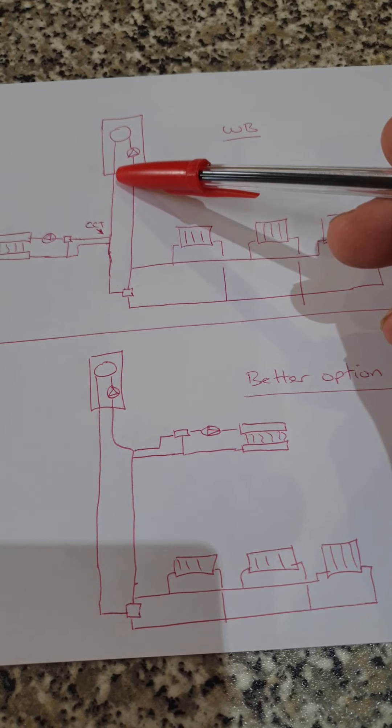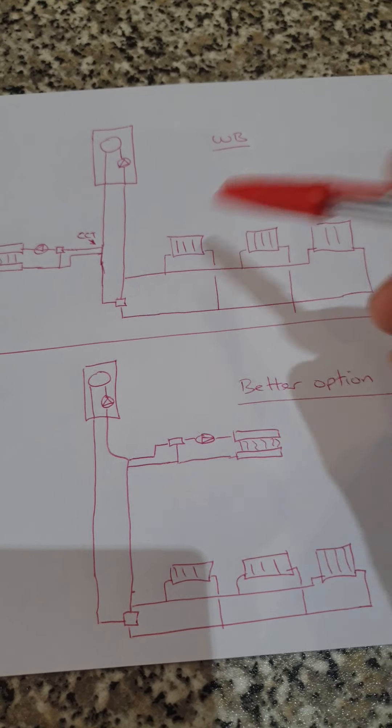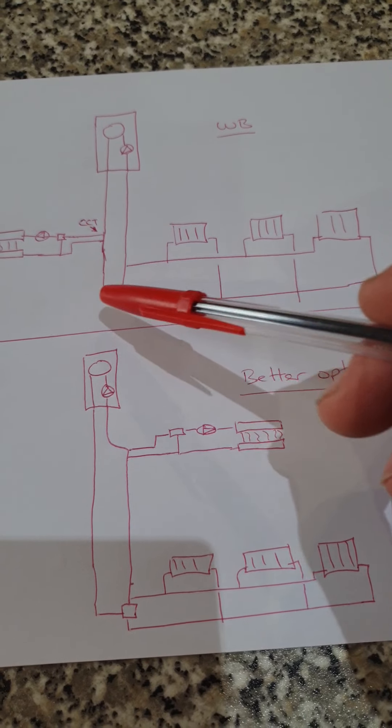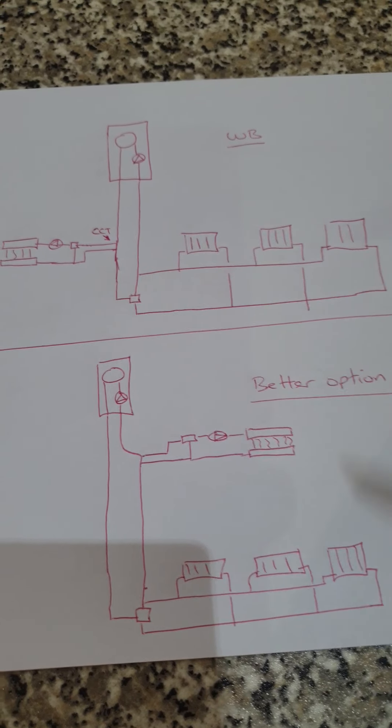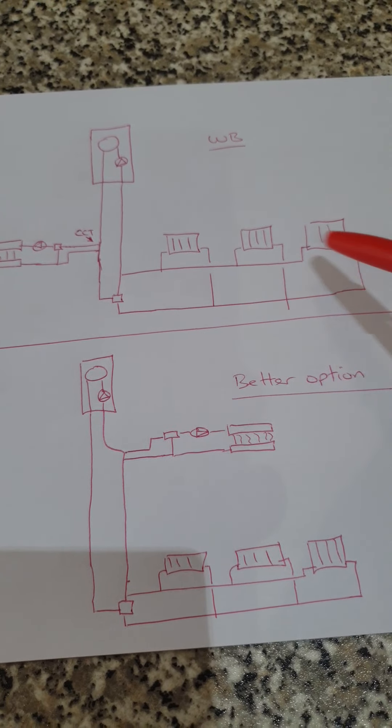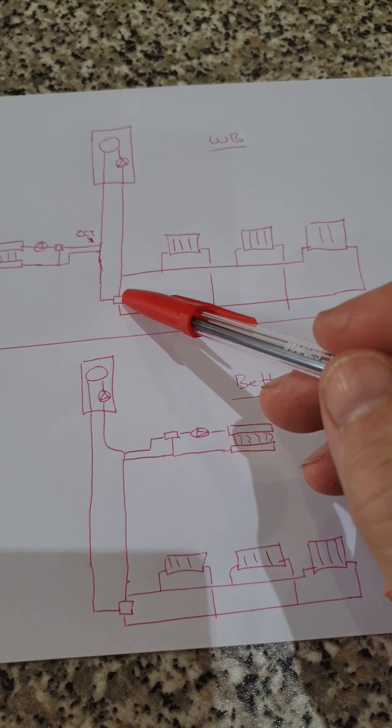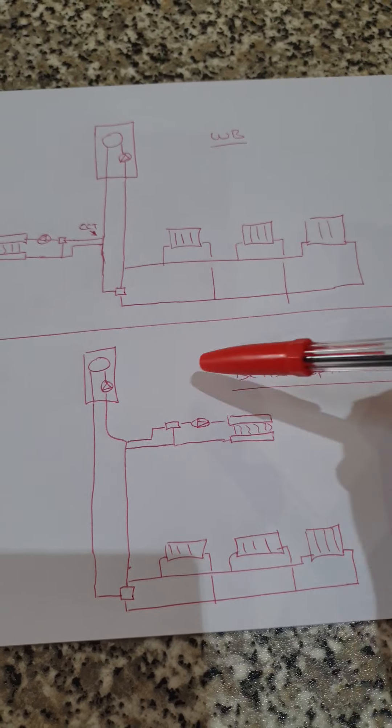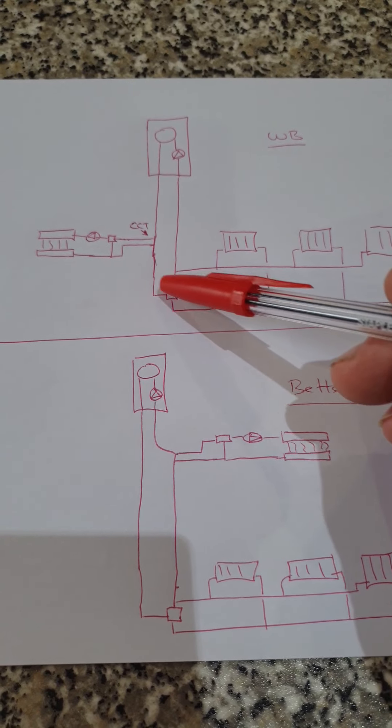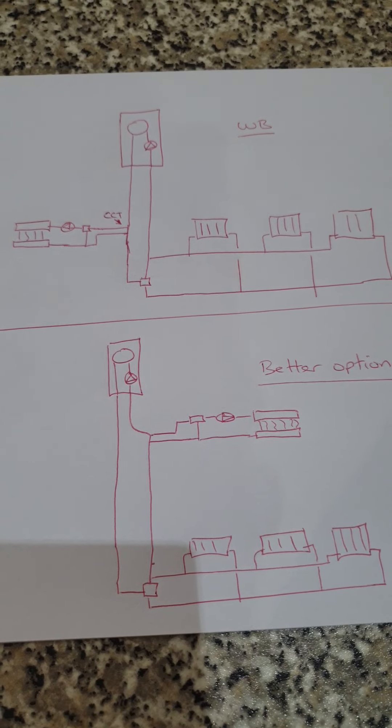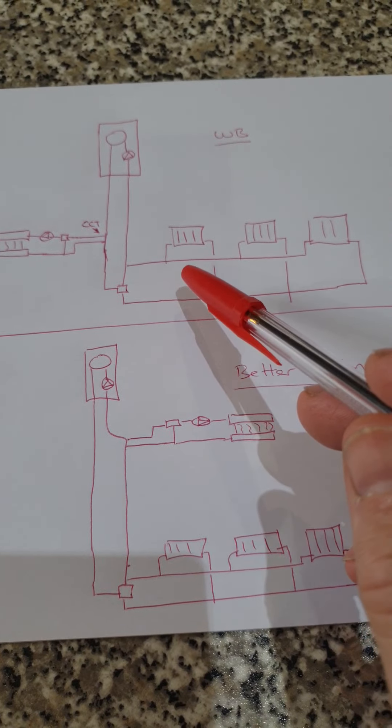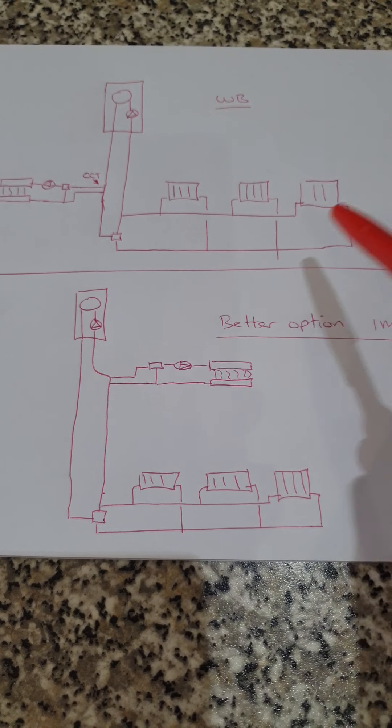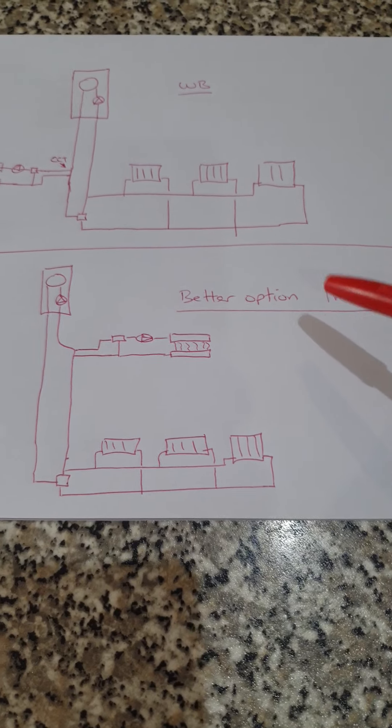And if you look at the system here, it'll allow the boiler pump to actually have its full pressure without any hydraulic interaction at this circuit due to these close coupled T's. To power the radiators as and when the diverter valve selects that circuit. If the diverter valve is diverting back to the boiler, this simply becomes like a standard loop and close coupled T's circuit without the heating circuit. And this adds it on. This is a clever solution. I would never have thought of it. And congratulations to Worcester Bosch for coming up with it.